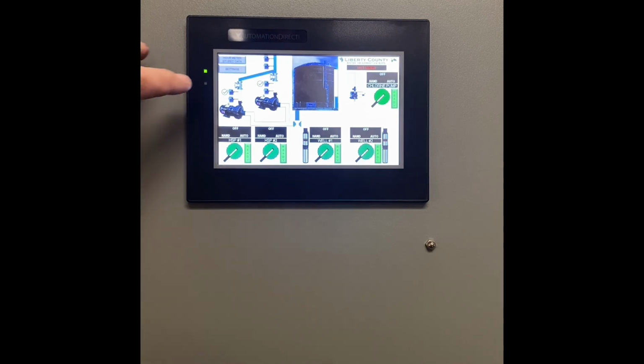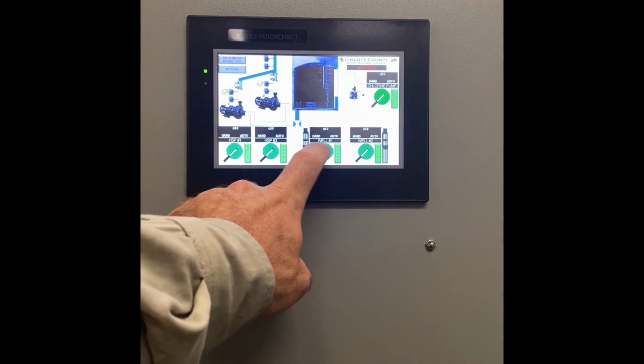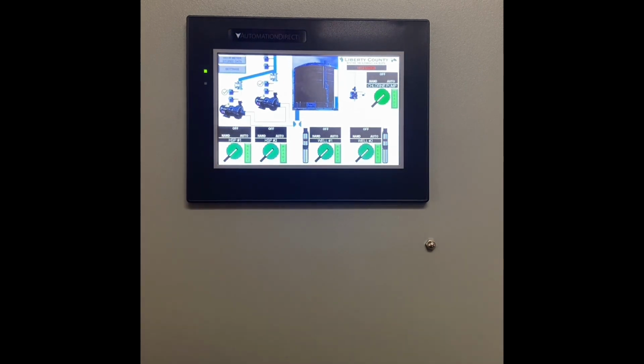What you'll also notice is now my check marks are on the upper 2 flow pressure switches. So if we use well number 1 as an example, when well number 1 is called for and running, it's looking to make sure that those pressure switches change state, indicating that there is sufficient flow from that well. If there is insufficient flow, the well will fail and it will give you a low flow failure. That low flow failure will pop up over the well itself. It will also give you a failure reset button and a failure acknowledge button. If you do not know the cause of the failure, the immediate thing to do is to press acknowledge.